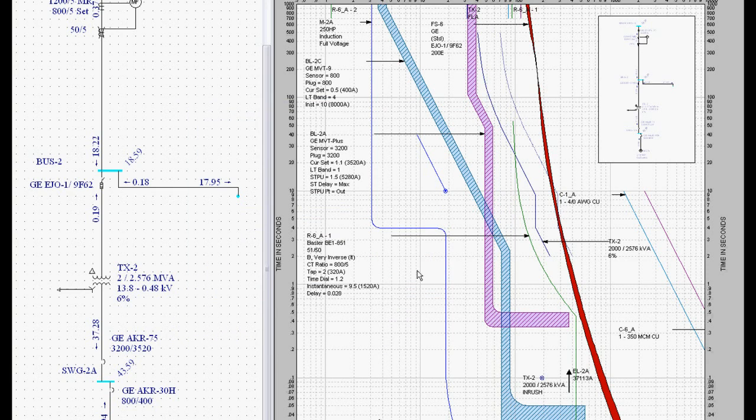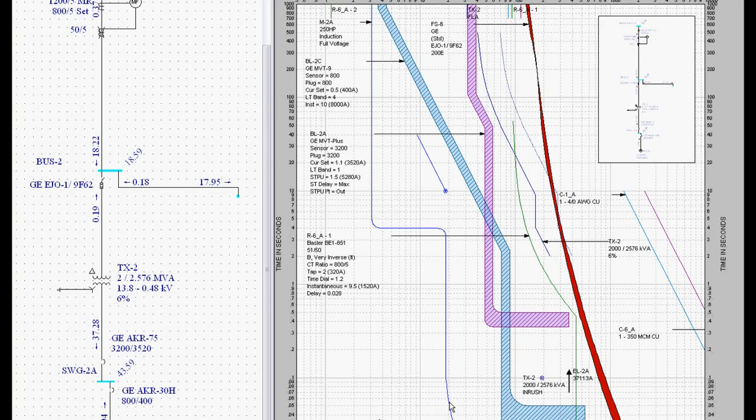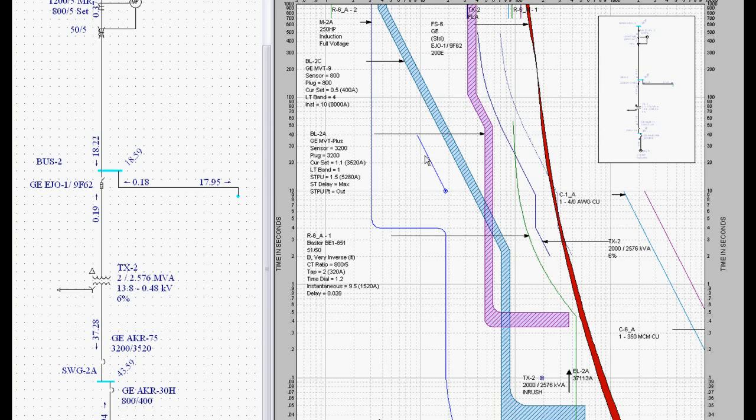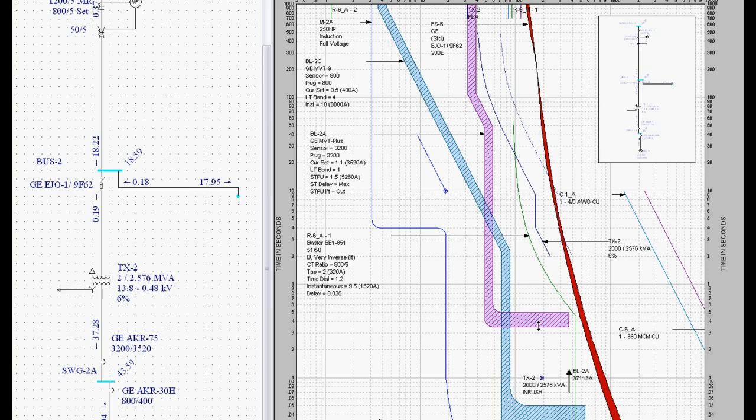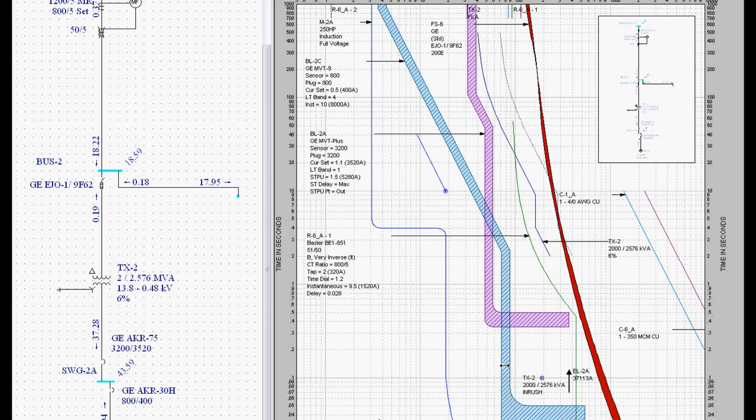So here are all the different protection boundaries. Our locked rotor asymmetrical, locked rotor symmetrical, acceleration time, full load amps, motor stall time, thermal damage curve. Here are my conductor damage curves. Everything that we need to set these protective devices is available to us. Now, how do we do that?